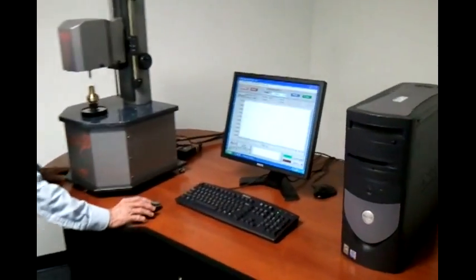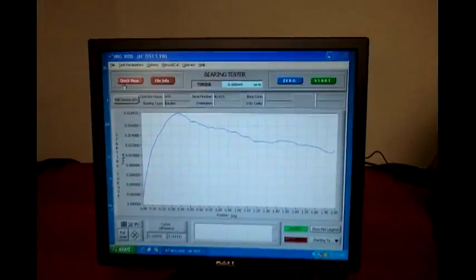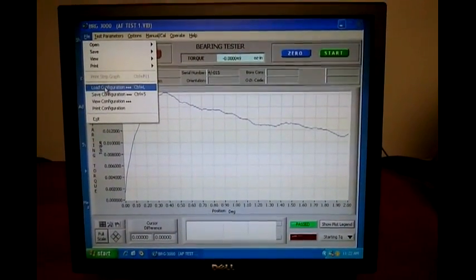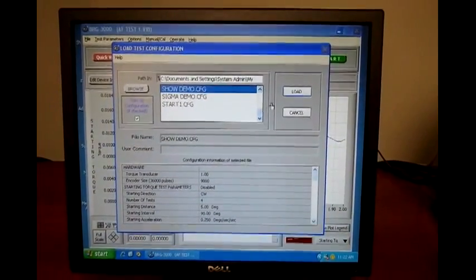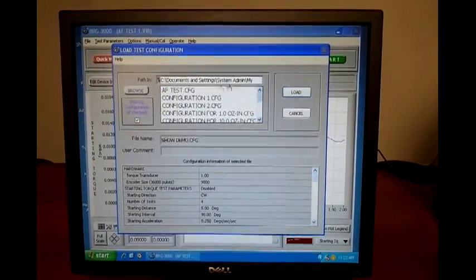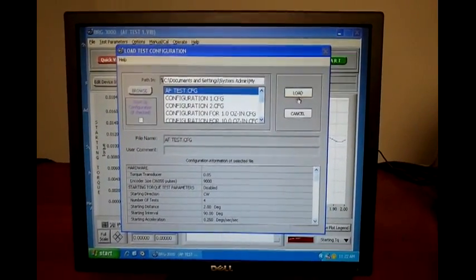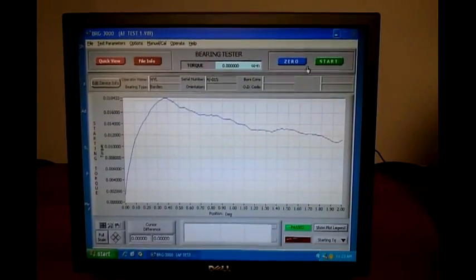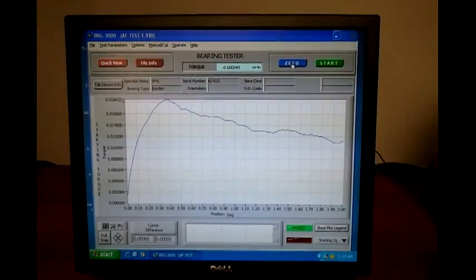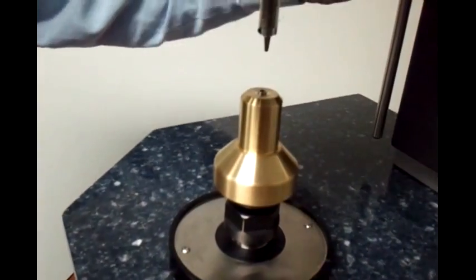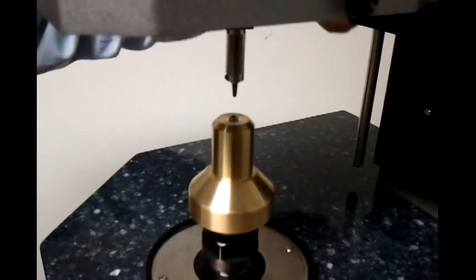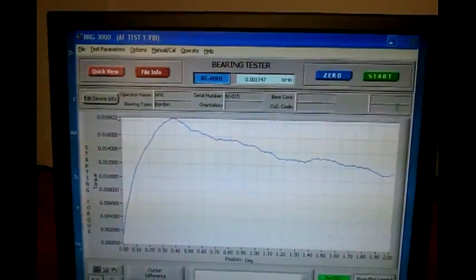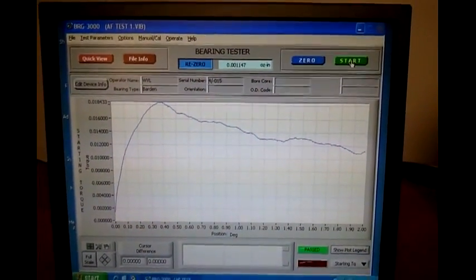First we go to the screen and select file once again and select load configuration. We go to the configuration we want to load, which will be AF test. We will load that. Now we will zero the transducer. We will come over and engage the tooling, then go back and tell it to start the test.